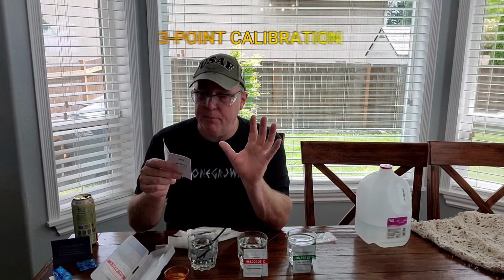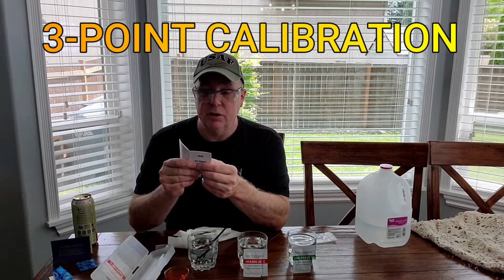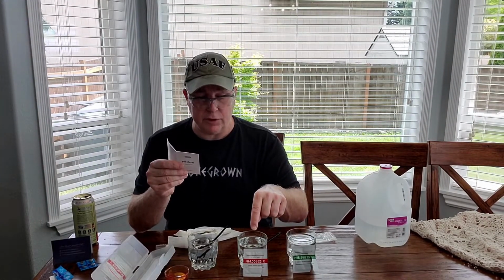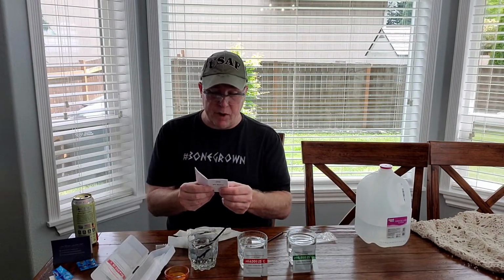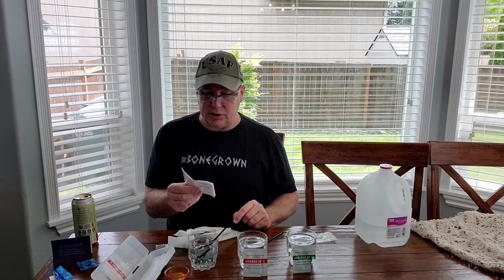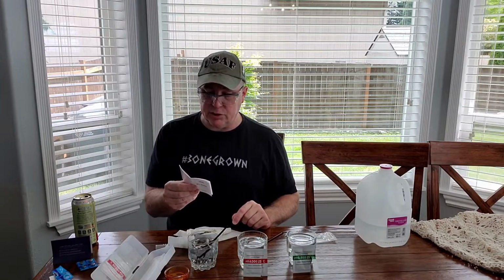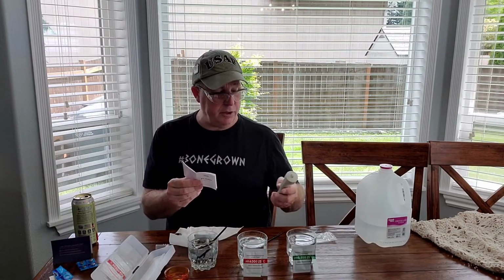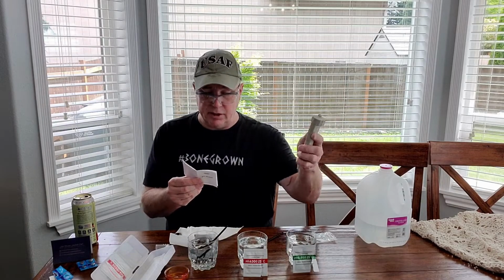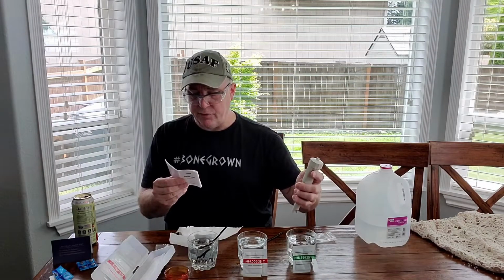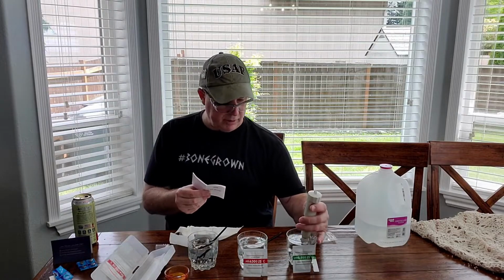So in calibration, it's also called the 3-point calibration, which means you should calibrate the meter with 6.86 solution, and then the 4.0 solution, and then move on to the 9.18 solution. And that's what we're going to do. So it tells me first to prepare my 6.86 solution, pH standard buffer solution. Press the on-off switch and turn it on. So I'm going to turn it on. Shake it appropriately. After the pH value is stable, press calibrate.